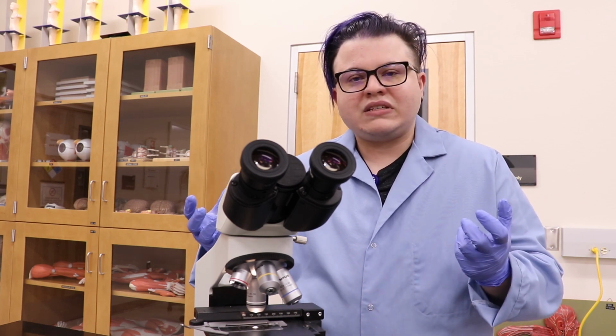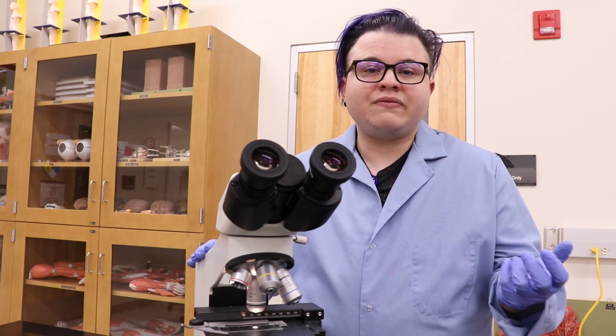Next, we'll go over some problems that you might find in the classroom setting that should be best left to the lab staff to address due to either the amount of time it takes to fix said problem or the extra tools necessary to fix it. The first one is a sticky stage, where you're having issues moving the stage itself in the XY plane. This is due to lack of lubrication in the gears itself and needs to be addressed outside the classroom.